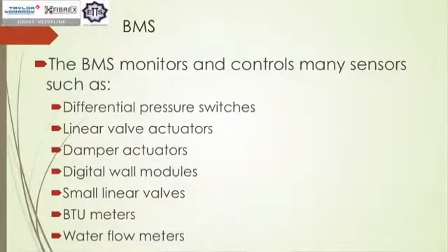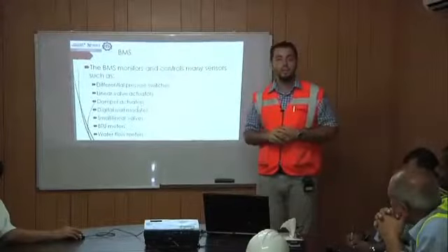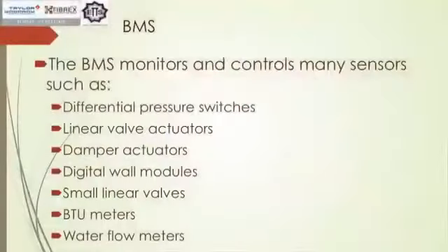We've got the damper actuators. These are monitored and controlled by the BMS, whether you want 60% fresh air, whether you want 20% fresh air, whether you want to close completely the fresh air and use your return based on the condition, external or the user-specific ones.